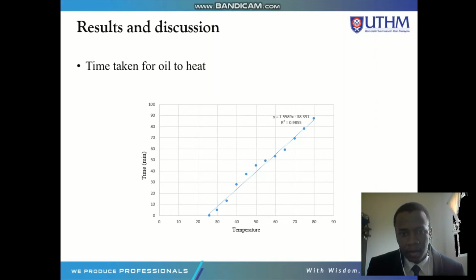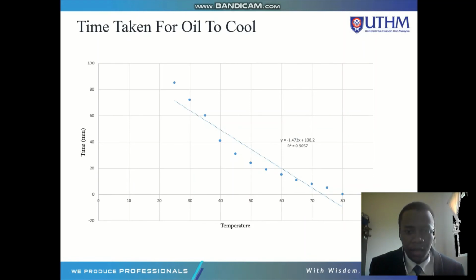1 hour and a half. Yeah, and then also we wait for the oil, and then we test the oil for it to cool down from 80 degrees Celsius until it reaches 25 degrees Celsius. You can see it takes also around 85 to 90 minutes.